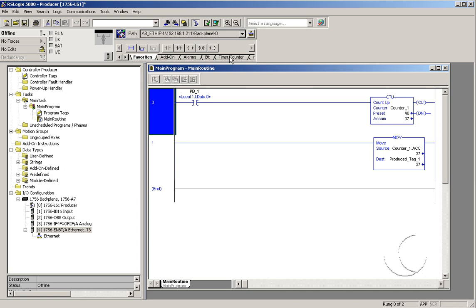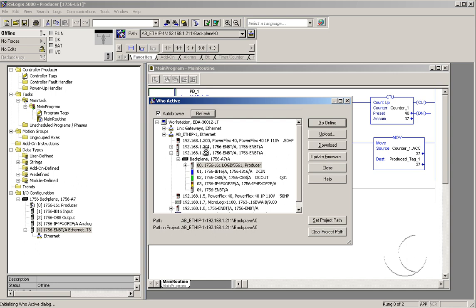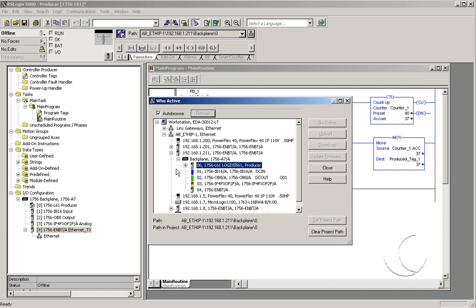The next step is to change the path within the project to match the new configuration of the controller. To do so, we simply go to RSWho. It's still showing the old connection that's no longer there — that remains in memory and the processor will attempt to find it. This hourglass will remain there for a while, so be patient. Don't start clicking and closing windows. It will eventually go away and allow you to browse through the AB Ethernet IP driver to the new processor that we just configured. At this point, you can see that the hourglass is gone. The first thing I want to do is clear the project path.